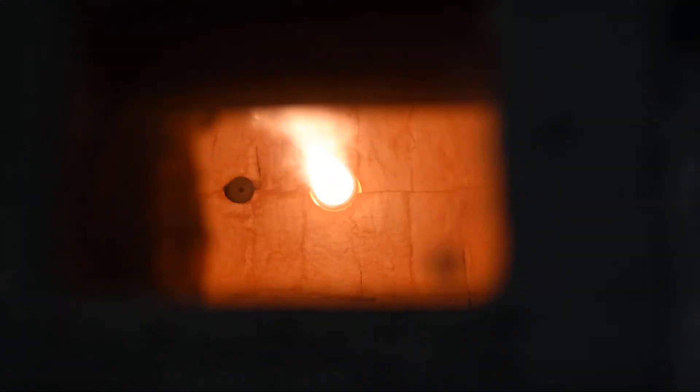The TwinBed II, at high fire with 10% excess air, creates a high velocity flame through the burner tile. Once the furnace reaches 1400 degrees Fahrenheit, auto ignition is achievable and low NOx mode can be enabled through the control panel.